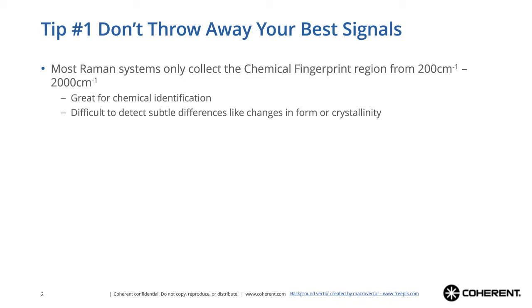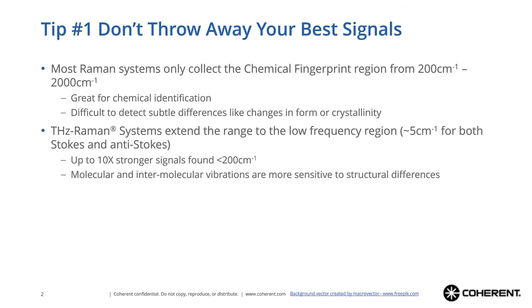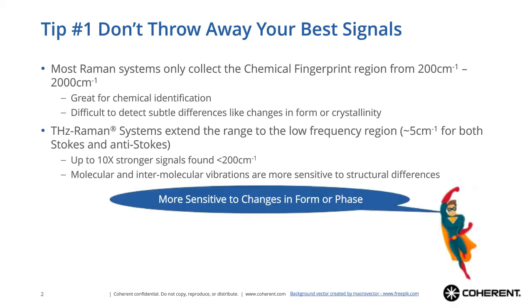With terahertz Raman systems, we actually extend the range of Raman to the low-frequency region down to about five wavenumbers for both Stokes and anti-Stokes. This gives you up to 10x stronger signals that can be found in the low-frequency region and allows access to molecular and intermolecular vibrations that are more sensitive to structural differences in the material. The low-frequency portion of the Raman spectrum typically thrown away in a conventional Raman system is actually more sensitive to changes in form or phase.